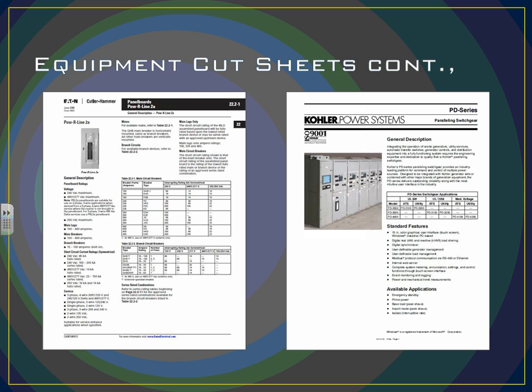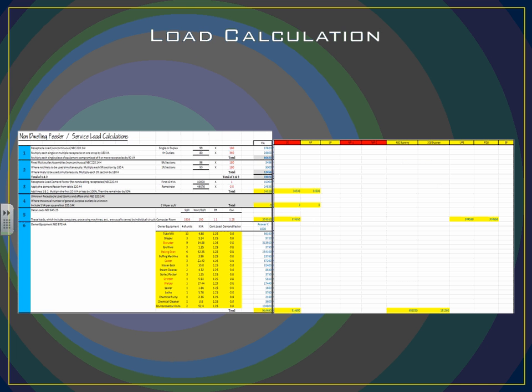This will be one of the panels that we use. This is a 100 to 400 amp panel, and that right there is a parallel switchgear that goes through the system. And now we'll break down into load calculations. For our load calculations, we use an Excel program with built-in macros, so that we can use what the NEC had for calculations. We set that up so that we can plug in the numbers based off of how many receptacles or how many light units we had, and then just let the computer drop that information down for us.